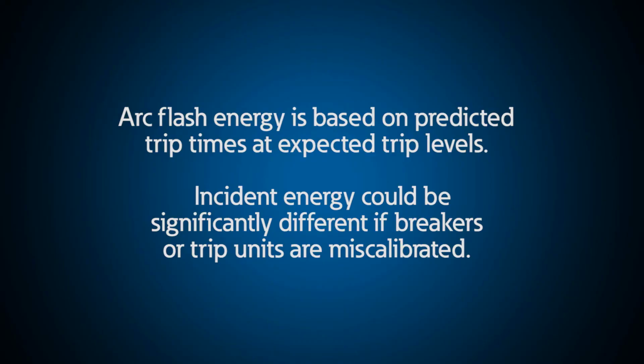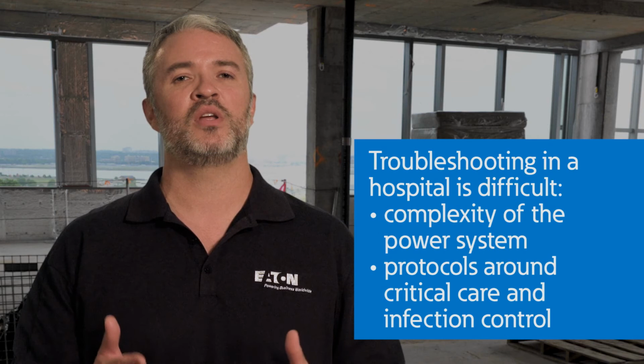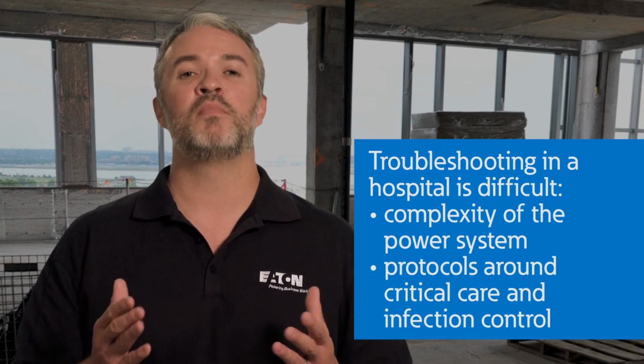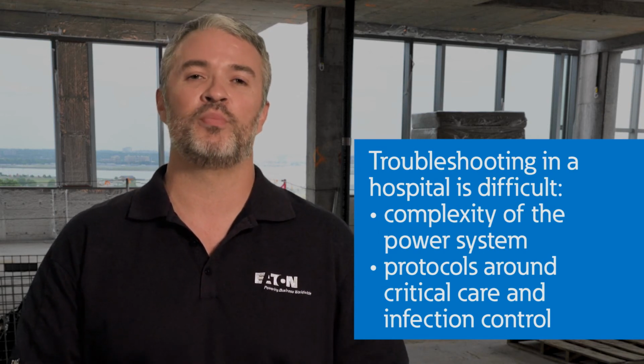As a contractor, this is very important because you would have used that arc flash incident energy level on the arc flash label to decide on PPE. When performing maintenance at a hospital, the scope of work is generally set before arrival, but that is not the case when troubleshooting. As a contractor, you should recognize that the task of troubleshooting an electrical issue in a hospital can take much more time than it would in a typical commercial building.